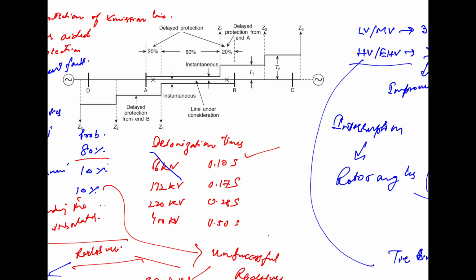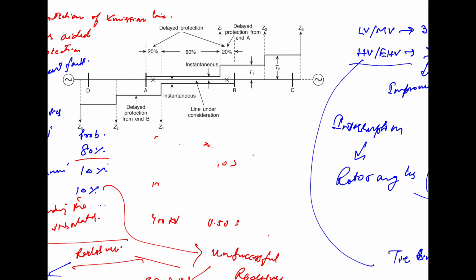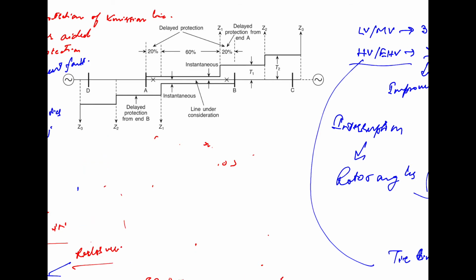This is explained in this figure, as we have also discussed in the previous chapter. That is, 60% protection is given. However, the protection is instantaneous for 20% of the line at each end: instantaneous from the local end but delayed for the remote end. So in order to implement the auto recloser, we need to augment the distance protection so that instantaneous tripping from both the ends for 100% of the line becomes possible. So what is the way out? We must augment the distance protection.